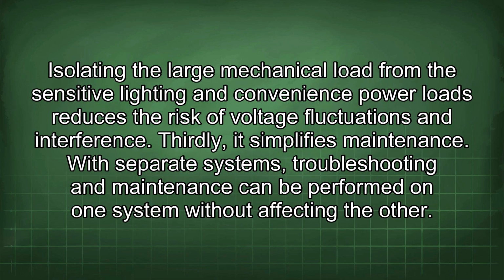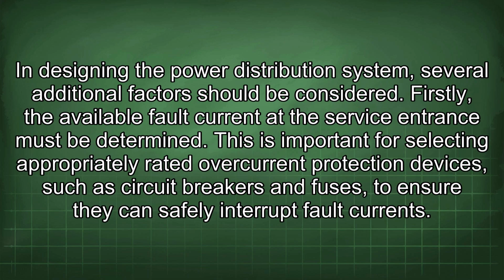Isolating the large mechanical load from the sensitive lighting and convenience power loads reduces the risk of voltage fluctuations and interference. Thirdly, it simplifies maintenance. With separate systems, troubleshooting and maintenance can be performed on one system without affecting the other. In designing the power distribution system, several additional factors should be considered.